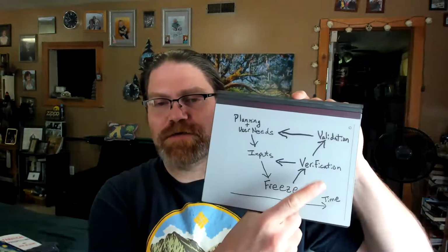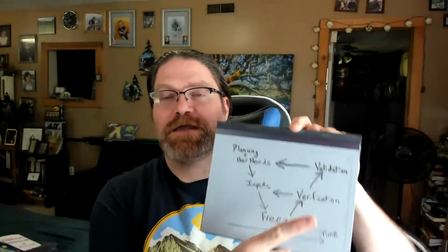Then we get into the next phase, which is the verification and validation testing. So verification first, typically, and then validation. It doesn't have to be that way. It could be in parallel, but there is a reason why sometimes you have to do verification first. If you have a high risk device that's going to be used in a clinical study, and your clinical study is the validation process, you need to make sure that your device is safe before you expose patients to it.